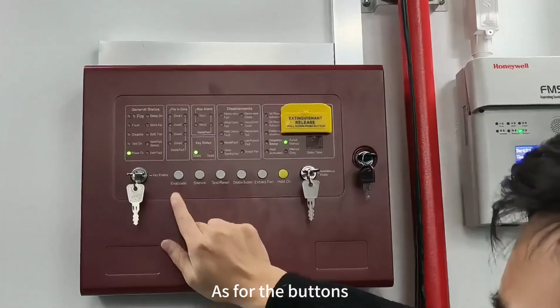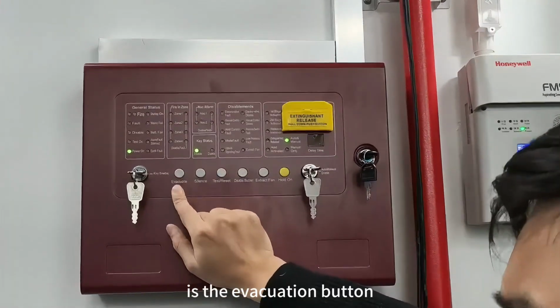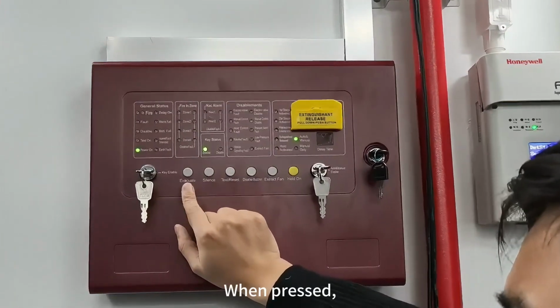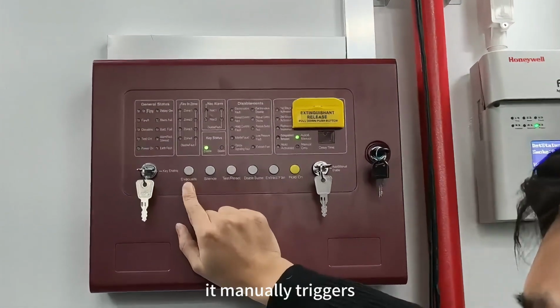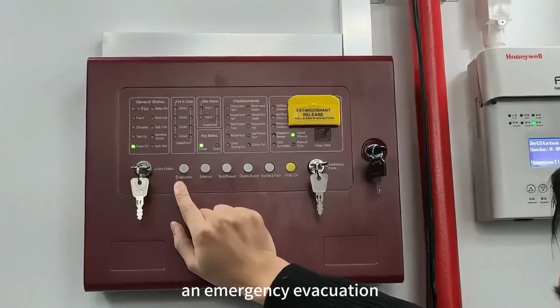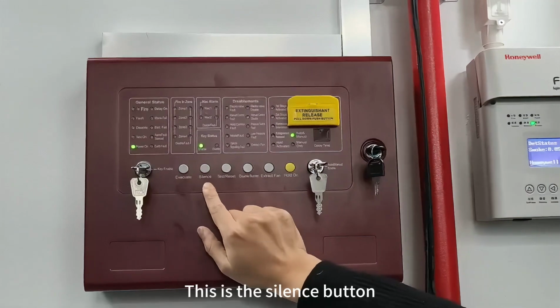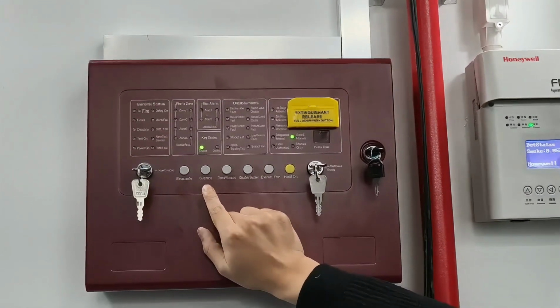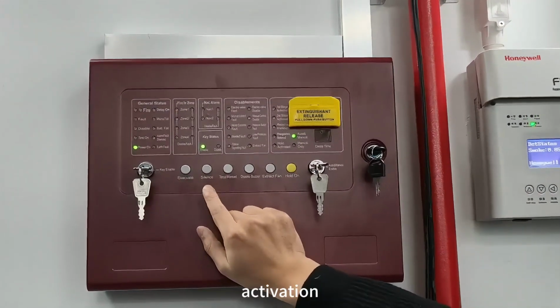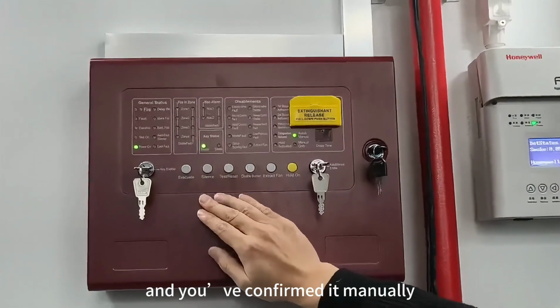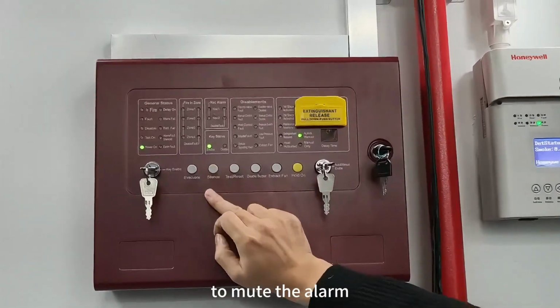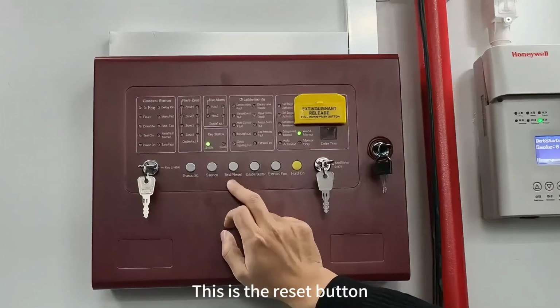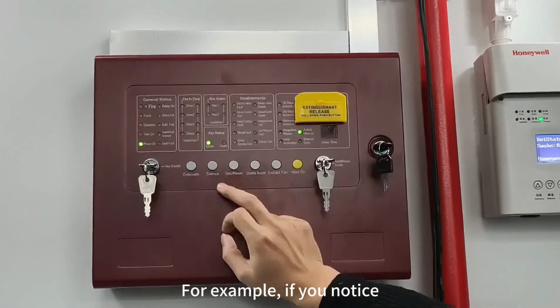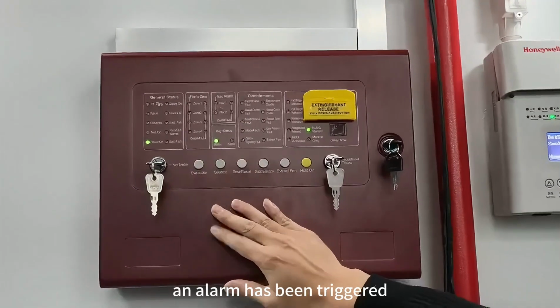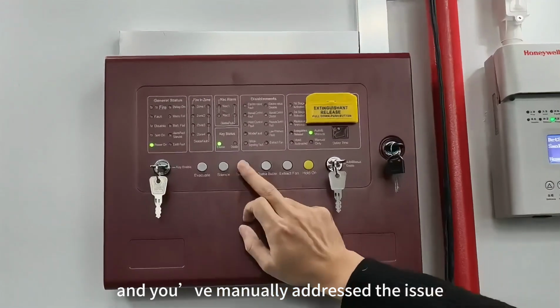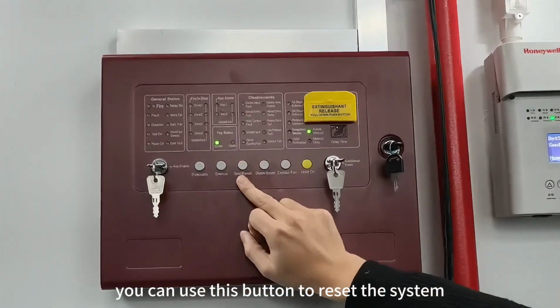As for the buttons, the first button is the evacuation button. When pressed, it manually triggers an emergency evacuation. This is the silence button. When there's an alarm activation, and you've confirmed manually, you can press this to mute the alarm. This is the reset button. For example, if you notice an alarm has been triggered, and you've manually addressed the issue, you can use this button to reset the system.